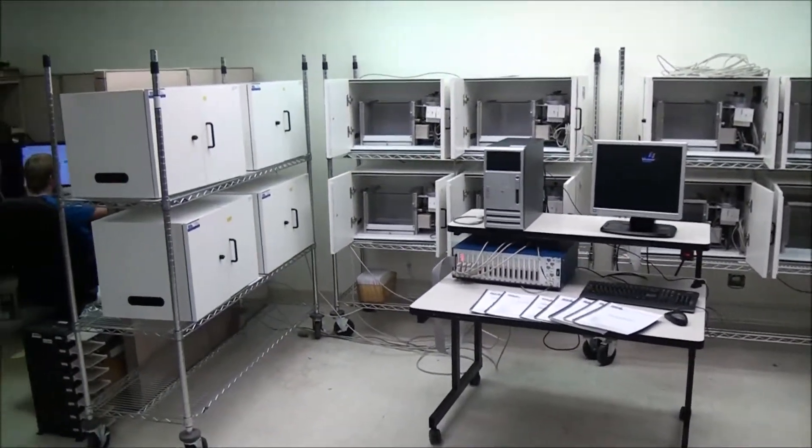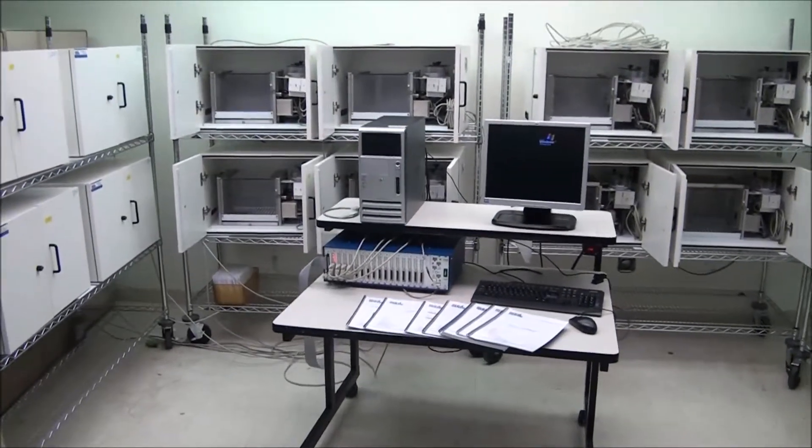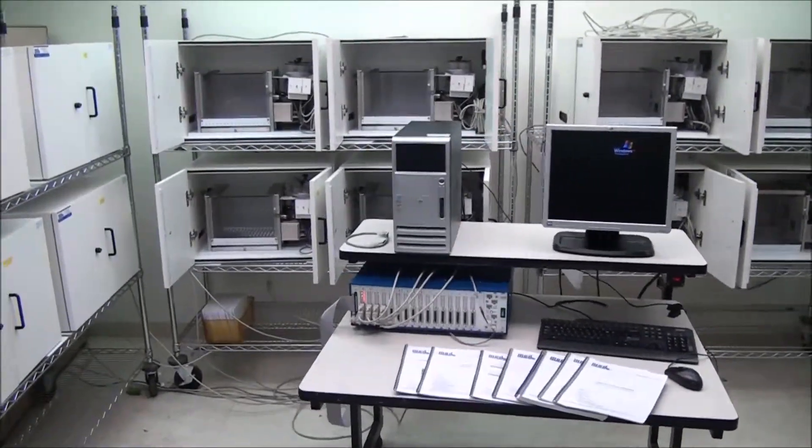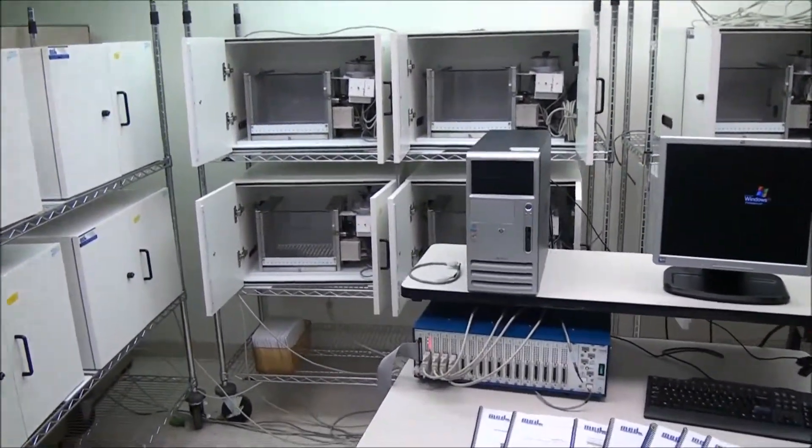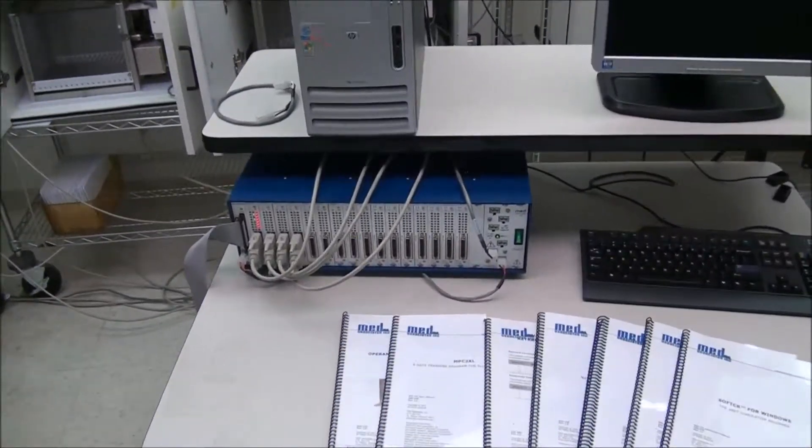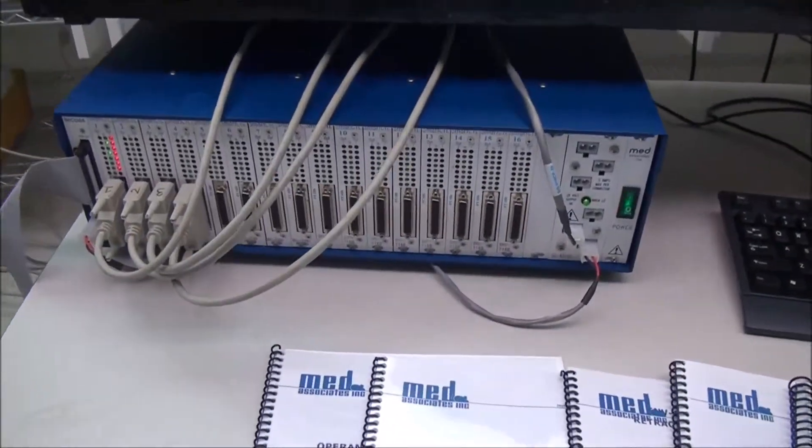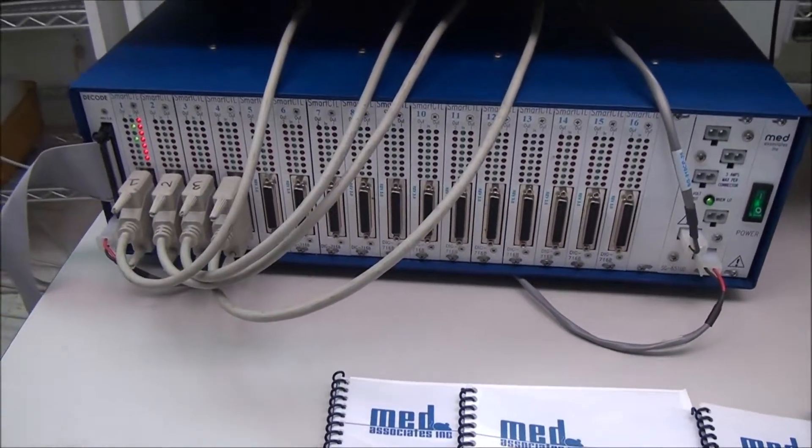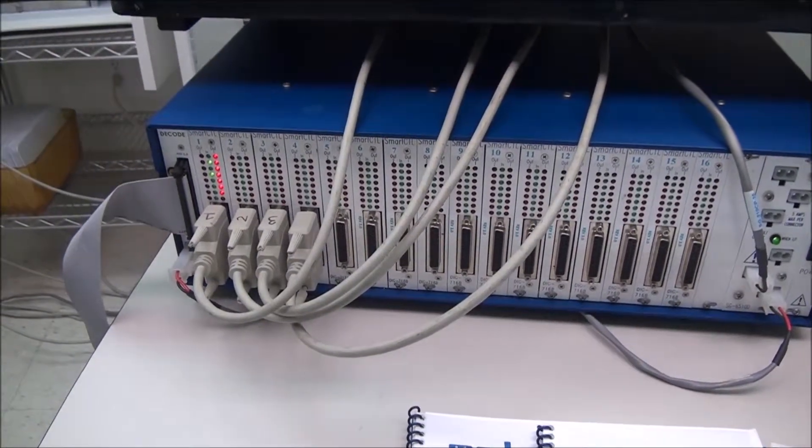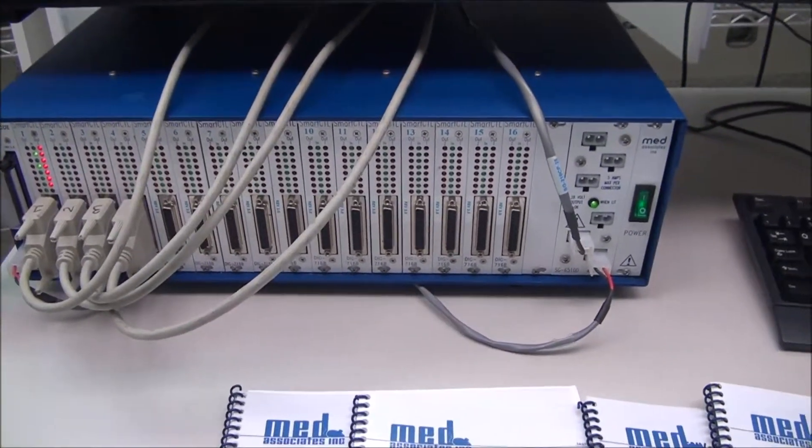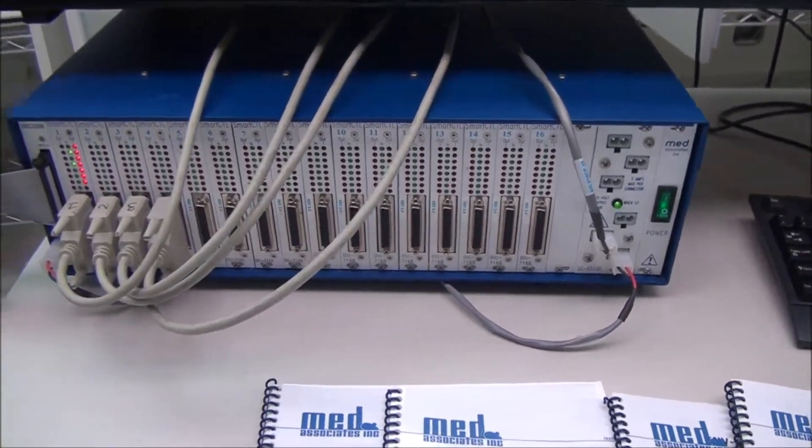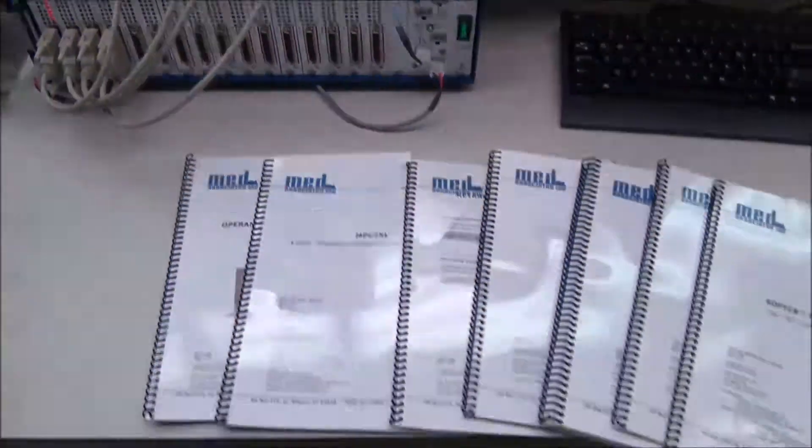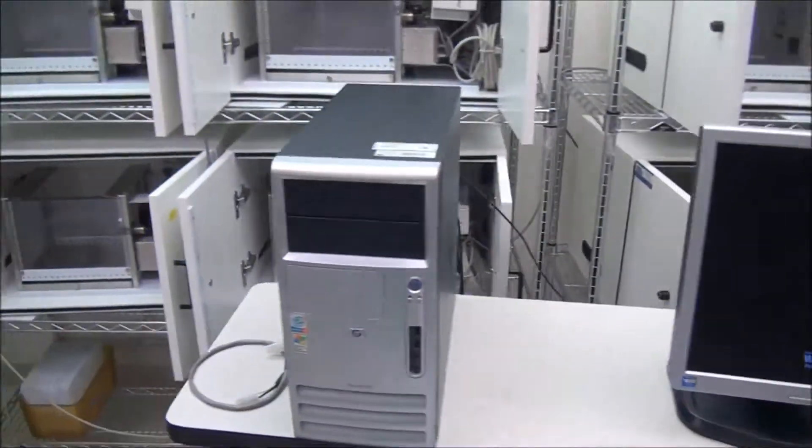This is one of the nicest systems we've had so far. You're going to see it has quite a variety of inputs and outputs. It has the control cabinet here with 16 of the 716B cards, and they each have 8 inputs and 16 outputs, so plenty of room to expand if you want. You've got all the manuals here, got the computer with the software installed.